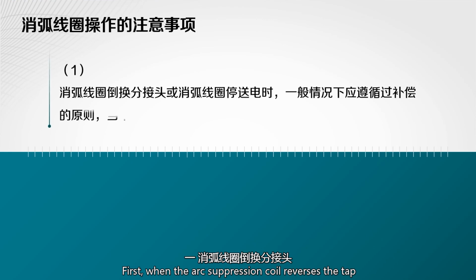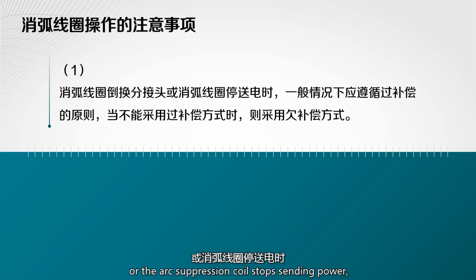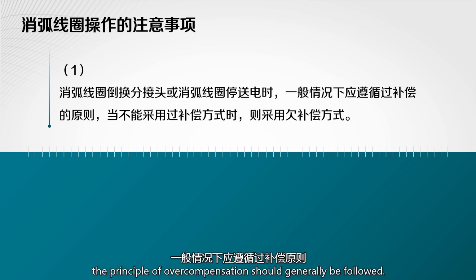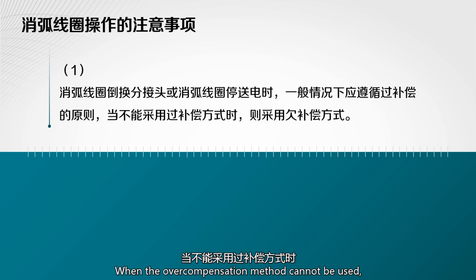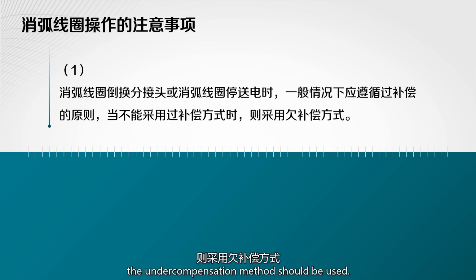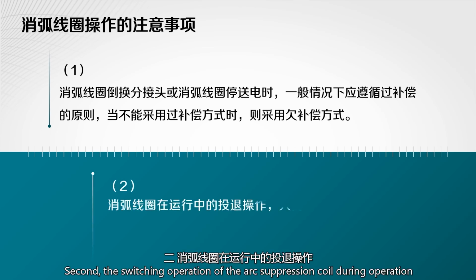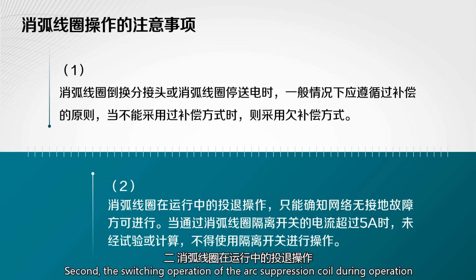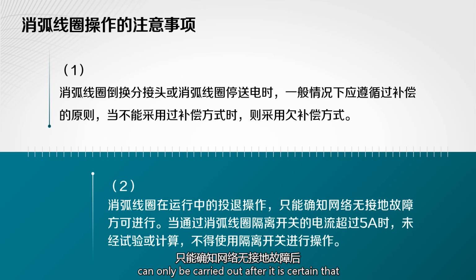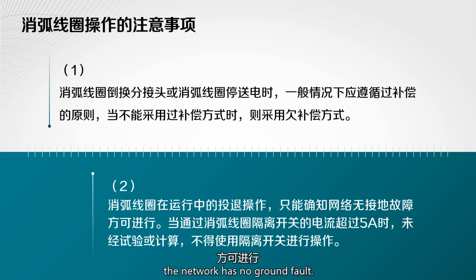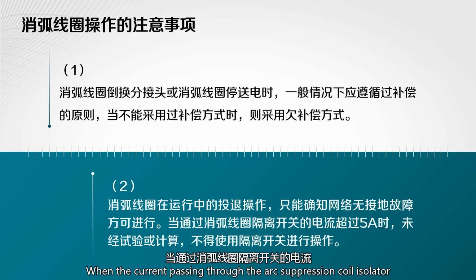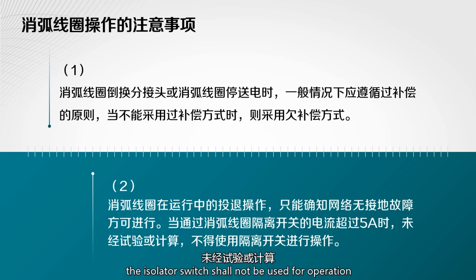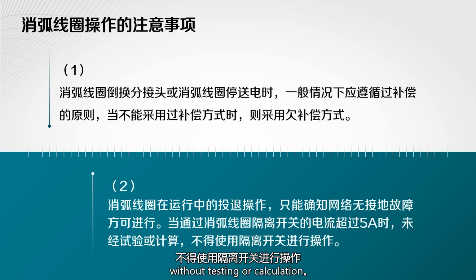First, when the arc suppression coil changes the tap or the arc suppression coil stops sending power, the principle of overcompensation should generally be followed. When the overcompensation method cannot be used, the undercompensation method should be used. Second, the switching operation of the arc suppression coil during operation can only be carried out after it is certain that the network has no ground fault. When the current passing through the arc suppression coil isolator exceeds 5 amps, the isolator switch shall not be used for operation without testing or calculation.